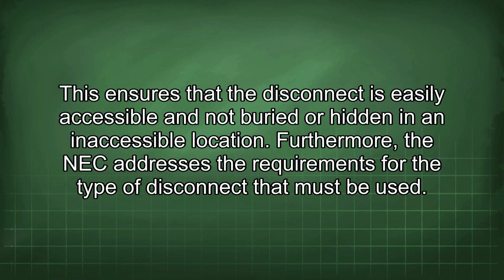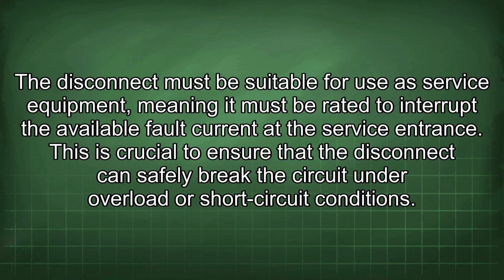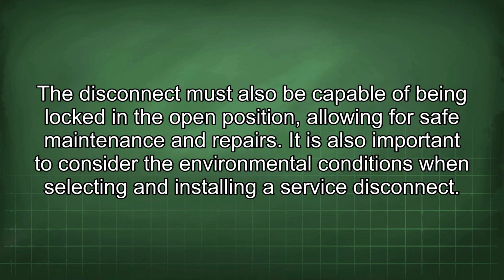Furthermore, the NEC addresses the requirements for the type of disconnect that must be used. The disconnect must be suitable for use as service equipment, meaning it must be rated to interrupt the available fault current at the service entrance. This is crucial to ensure that the disconnect can safely break the circuit under overload or short circuit conditions. The disconnect must also be capable of being locked in the open position, allowing for safe maintenance and repairs.